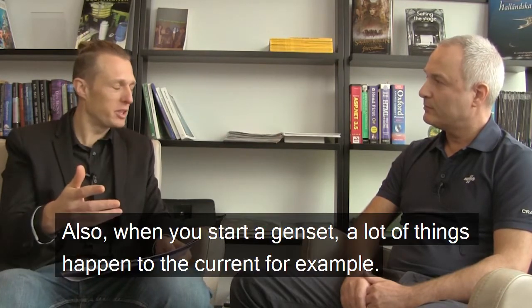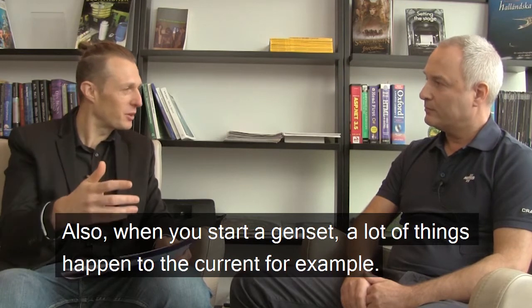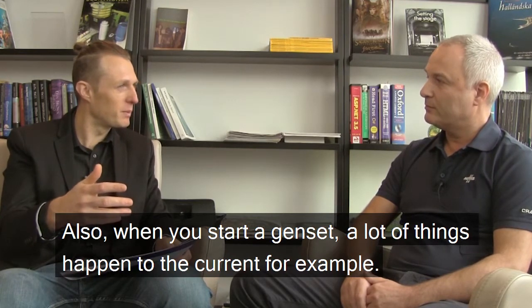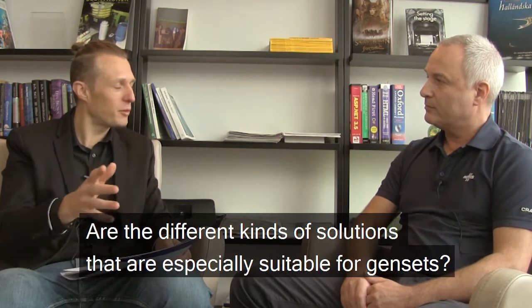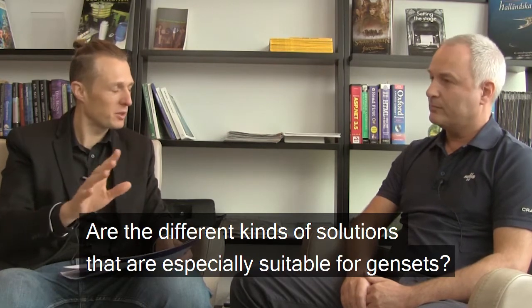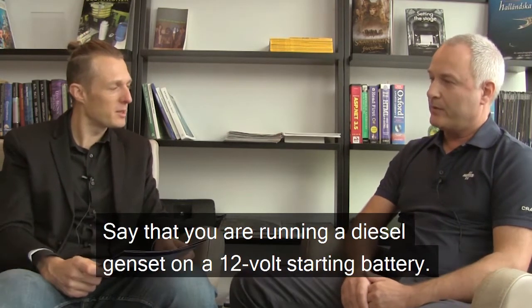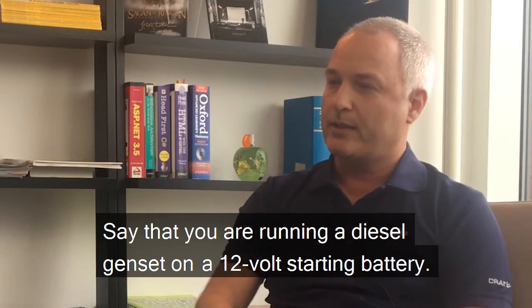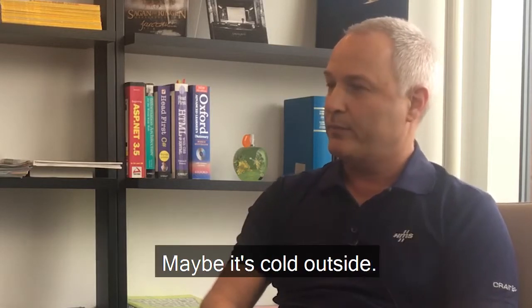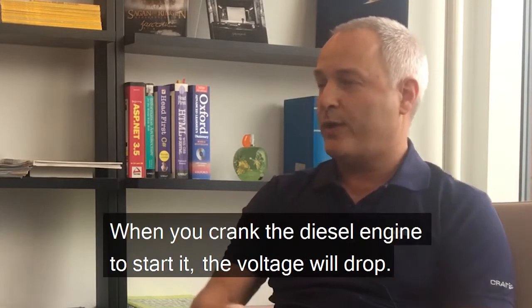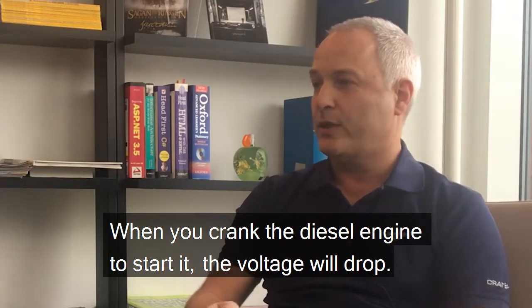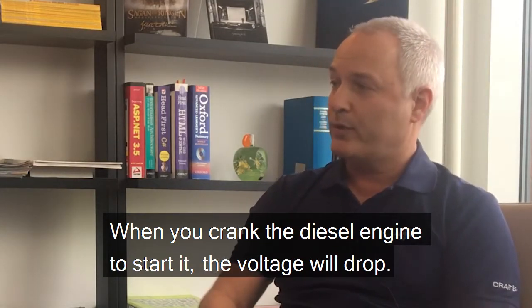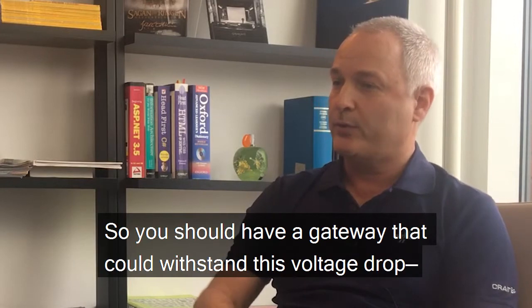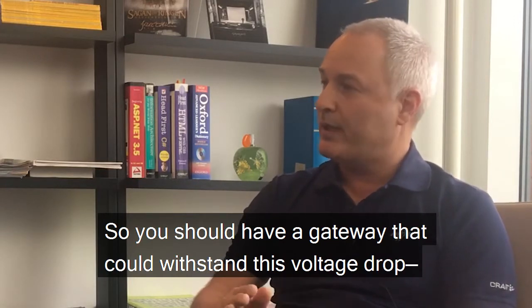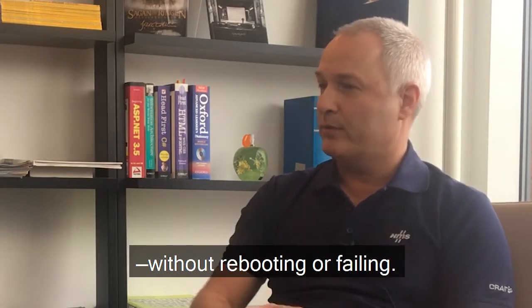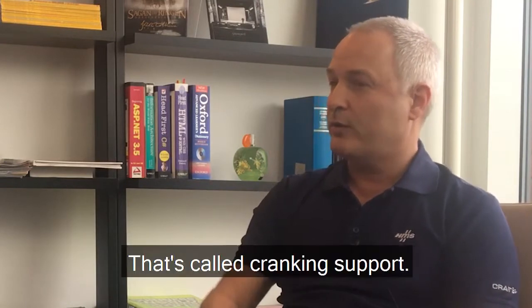Also, when you start gensets, a lot of things happen to the current, for example. Are there different kinds of solutions especially suitable for gensets? Say you're running a diesel genset on a 12-volt starting battery. Maybe it's cold outside - when you crank the diesel engine to start it, the voltage will drop. So you should have a gateway that can withstand this voltage drop without rebooting or failing. Oh, okay, that's called cranking support.